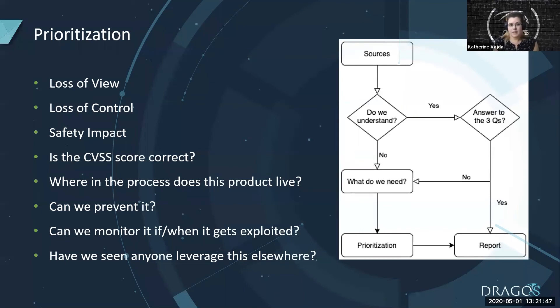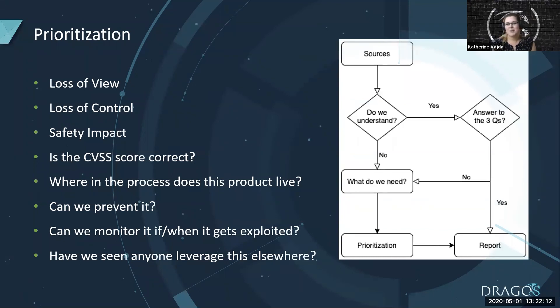Does the vulnerability actually affect the operator's view of the process? This could be a denial of service to an HMI. Does it affect the operator's ability to control the process? This could be a denial of service to the controller itself. Is there a safety impact? This could be a vulnerability in safety instrumentation. Is the CVSS score correct? Based on what we know about the vulnerability, does the score make sense? We go through the CVSS scoring descriptions and examples to double check that the score matches the vulnerability, and when it doesn't, we correct it. Then we ask where in the process does this product or device actually live — that determines its placement in the Purdue model. And can an attacker actually leverage this vulnerability, or can we at least monitor it if an attacker tries? We also check if anyone has actually leveraged it elsewhere, looking at proof of concepts, checking if our activity groups leverage them, and communicating with our customers.